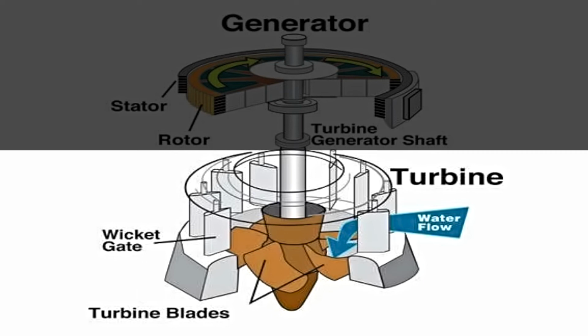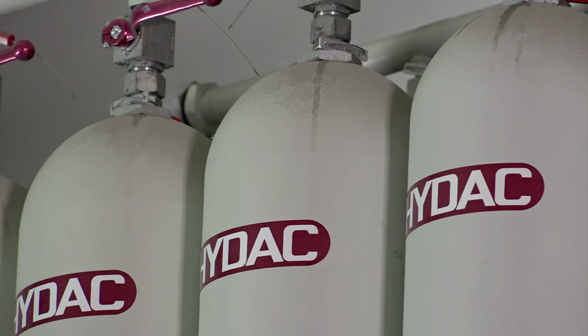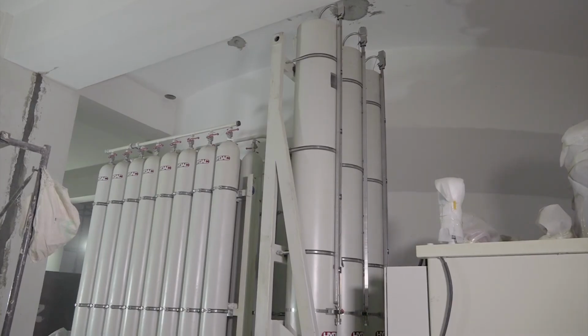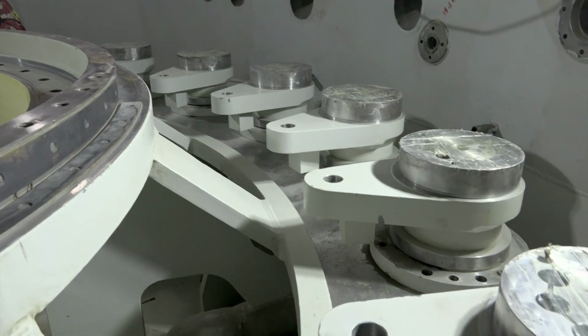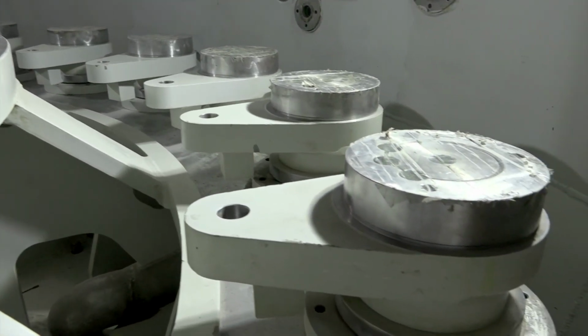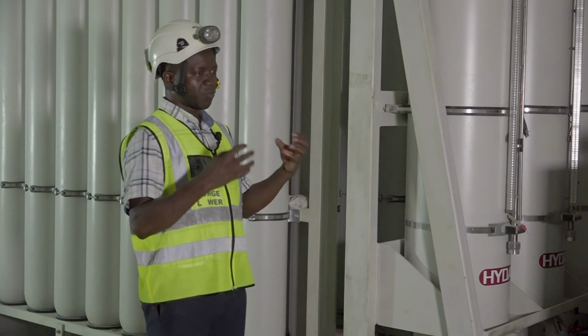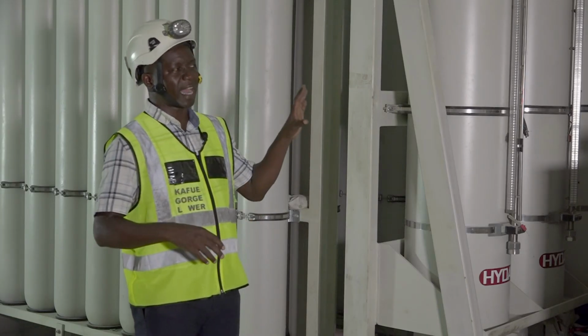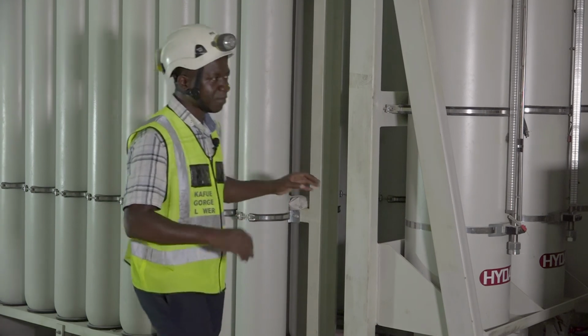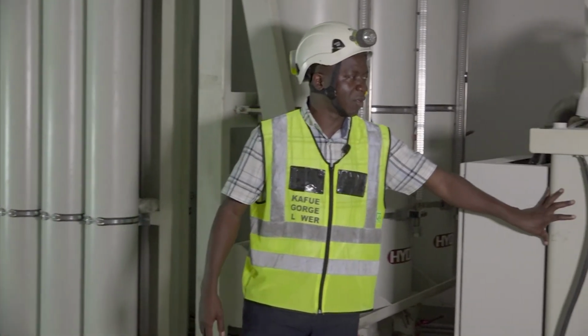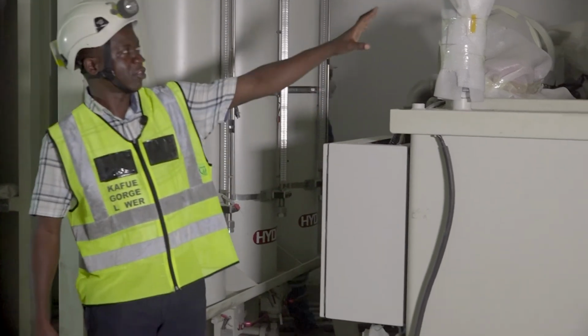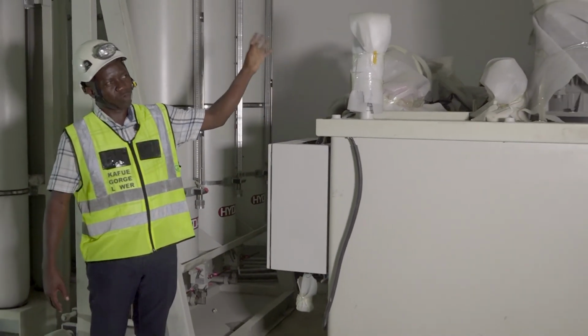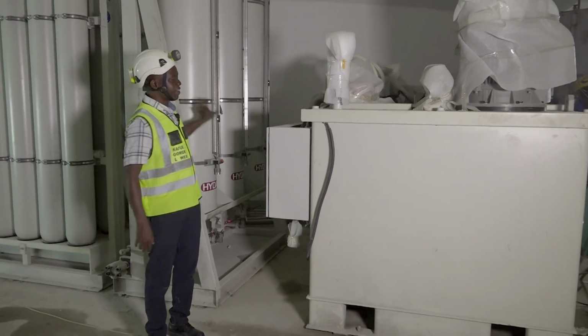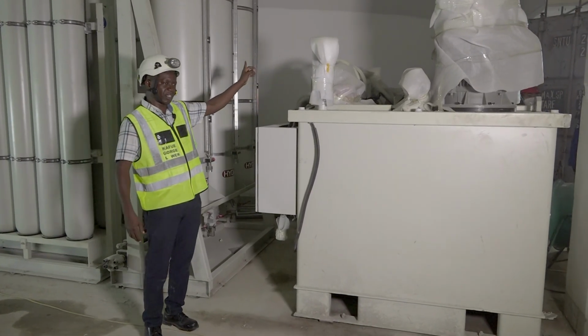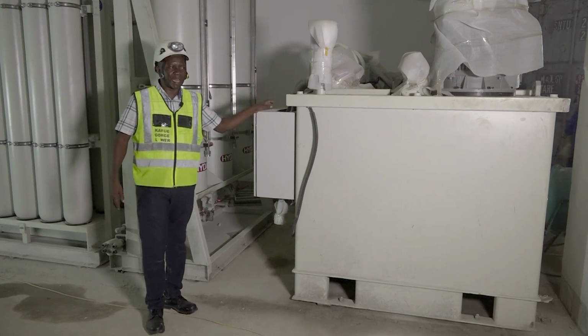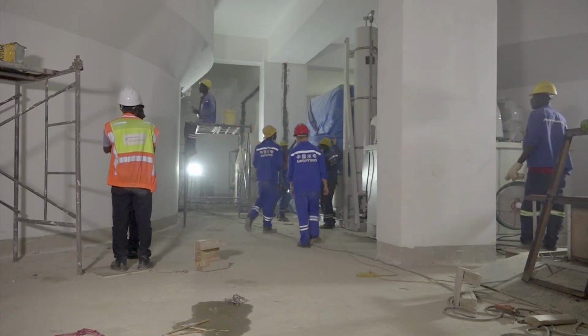The servo motors that operate the guide vanes are supplied with hydraulic oil from the hydraulic power unit at high pressure. The guide vanes regulate the flow of water to the generator units. For us to be able to open and close, we are using hydraulic oil, which is coming from this station. Here we have a tank. This will have hydraulic oil. Then there are 2 AC-powered pumps, which are pumping the oil to the vessels here. Then there's a standby pump, which is DC, in case we lose AC power supply, because this is critical equipment, we still need to be able to run.